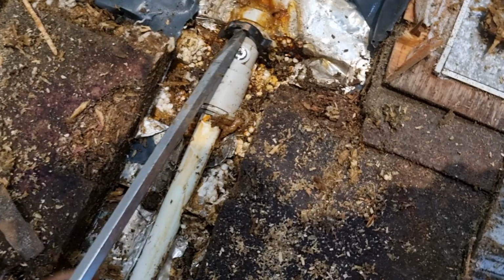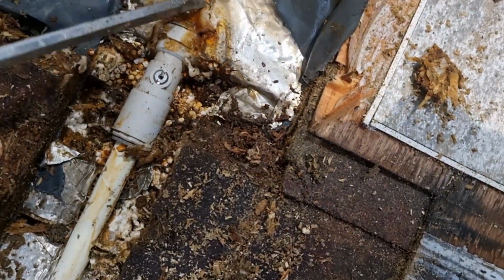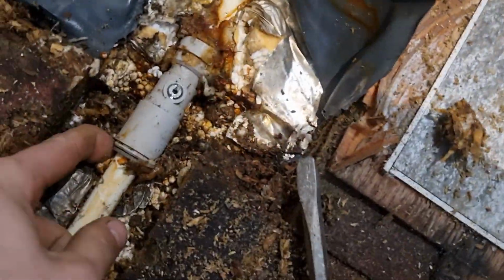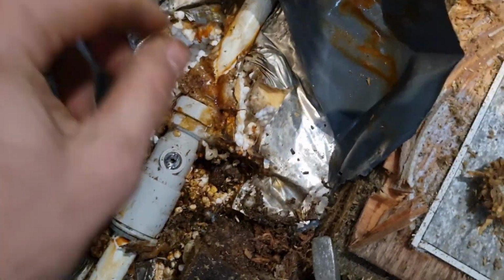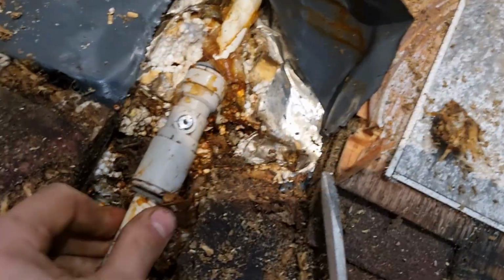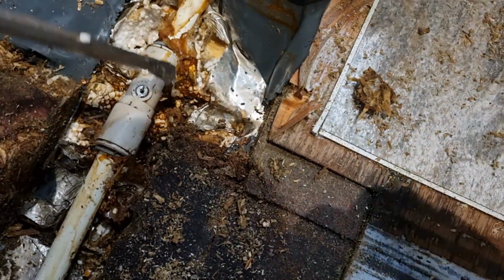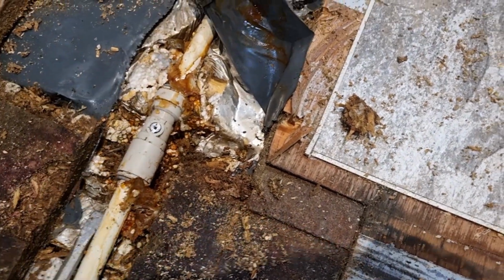So somebody's buried an isolation valve on the underfloor heating under the floor, and that's now leaking. I can't tell if that's Uponor or Speedfit. But if it is Uponor, they've used the wrong valve anyway. So we'll get that cut out. It is Uponor, that's not Speedfit. Jacob's filling the valve, I've got to fix the leak. We'll get that cut out.